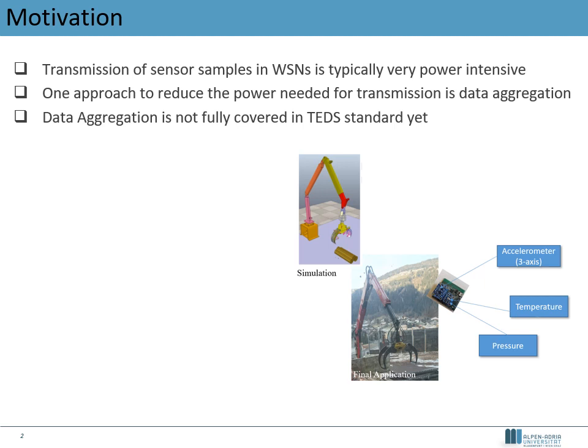One example of such electronic datasheets are the IEEE 1451.0 Transducer Electronic Datasheets, or TEDs for short. These are stored in a machine-readable format on the transducers themselves and can be retrieved by a base station, which is called the Network-Capable Application Processor, or NCAP, in the standard, via specialized commands.